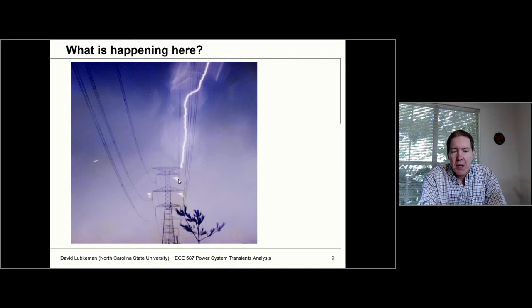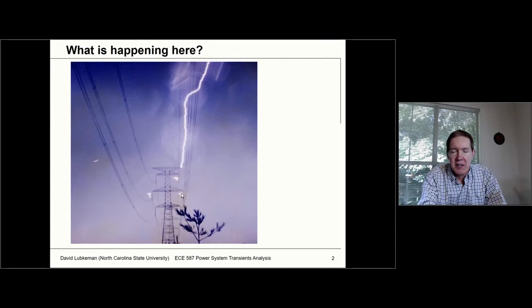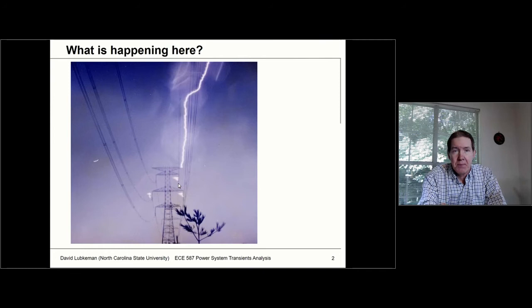When the voltage differential between the ground and the insulation becomes high enough, we get a failure of that insulation, causing a flashover. You can see this was such a powerful bolt that it injected so much current that it caused high voltages not only on one phase but also on the other phases, causing a flashover and a short circuit that needs to be cleared by circuit breakers.